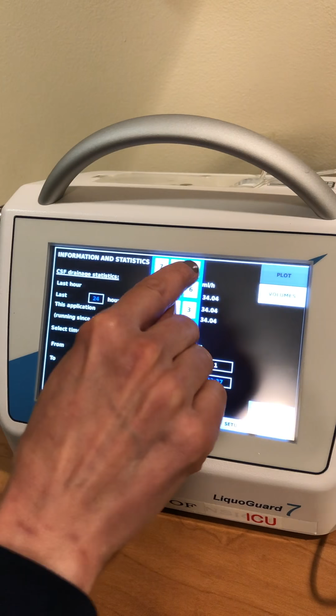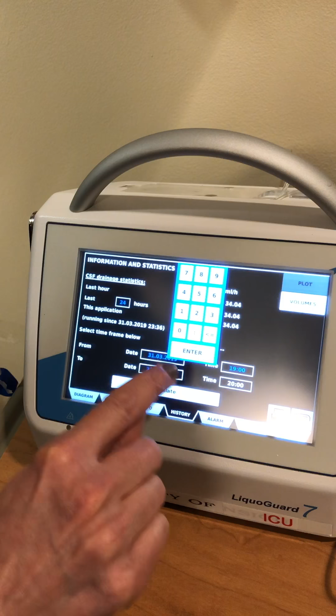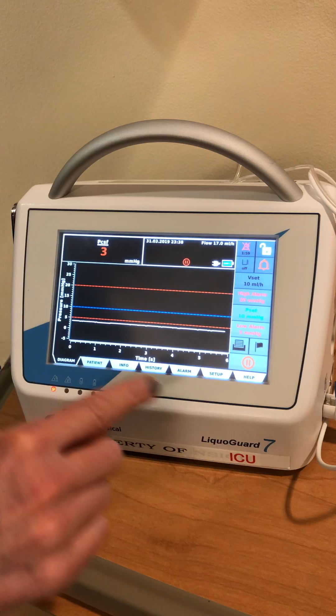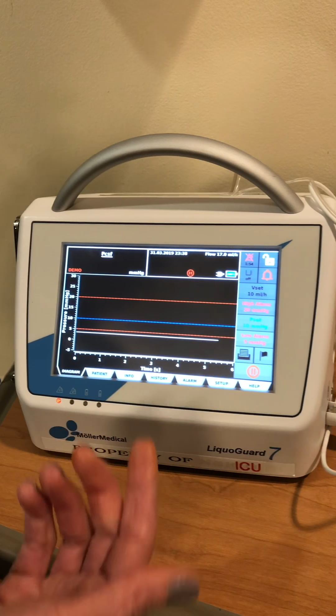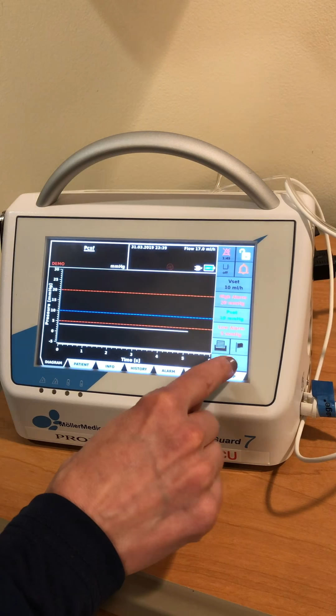So when you come in here to check your volume, how much it's put out in the last hour, you go to history, volumes, and then you're going to have to manually put in here. So for instance, we'll go from 1900, you go 19 semicolon 00, enter, and then to 2000, don't forget the semicolon, enter, and then you would hit calculate, and that'll show you what it put out for the last hour. So you should be getting around 10 cc's an hour, maybe like 9.8, but something around there.